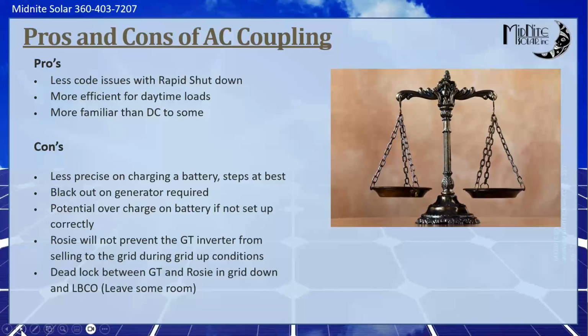If you can get into something a little bit DC coupled, with a charge controller, or an all-in-one that has an MPPT input, it will of course charge the battery from the solar directly because it's DC coupled. But if it's purely AC coupled, that is a deadlock you can get into. So it is important to set that low battery cutout to a little bit higher standard.